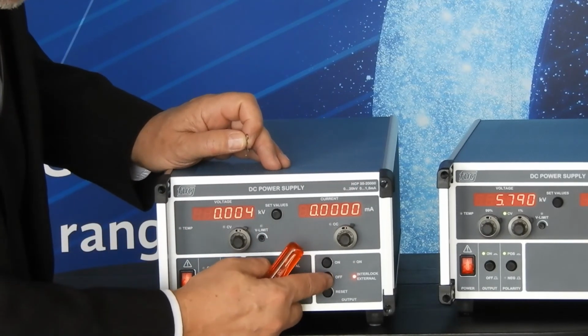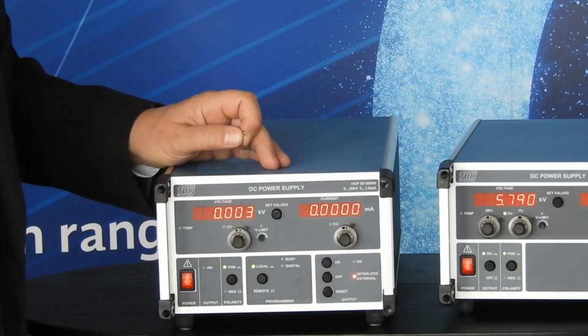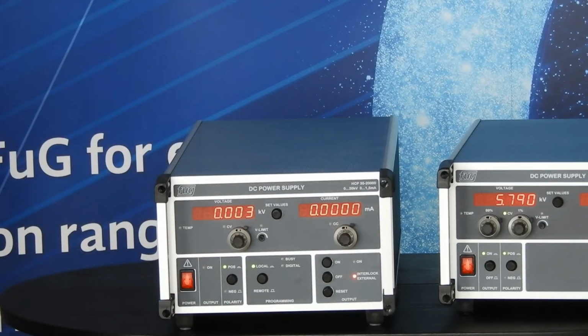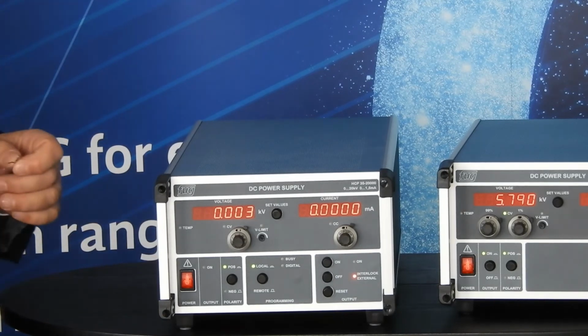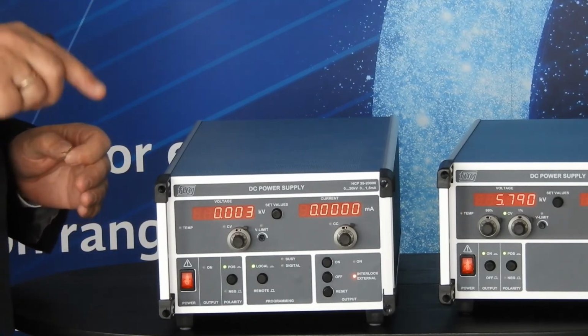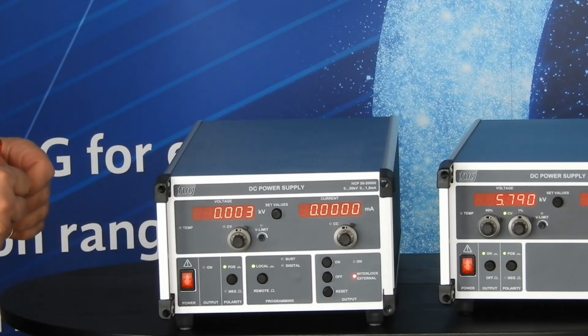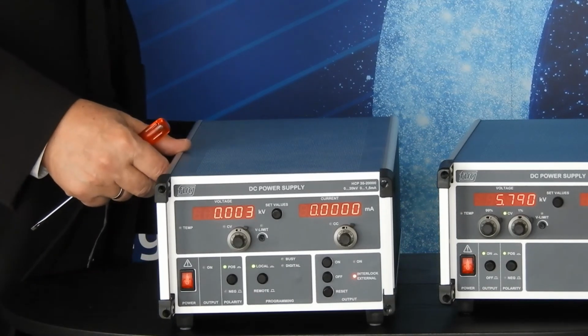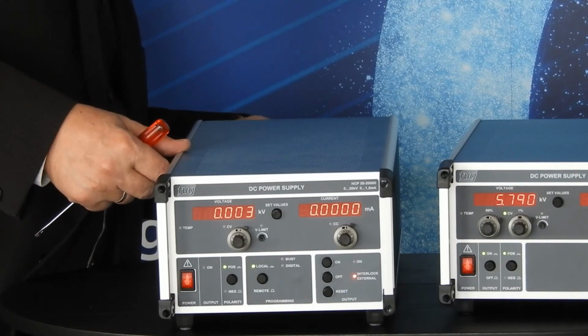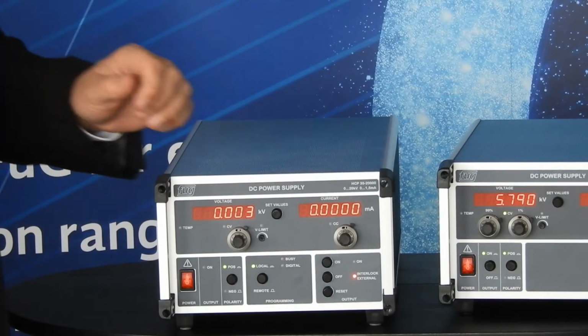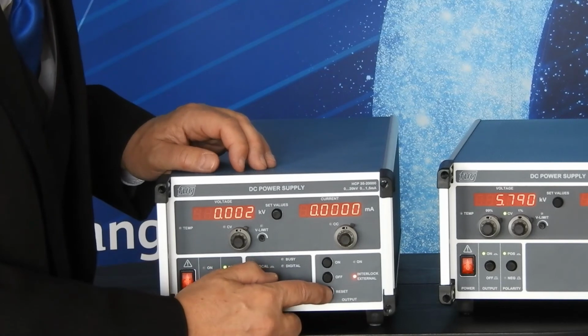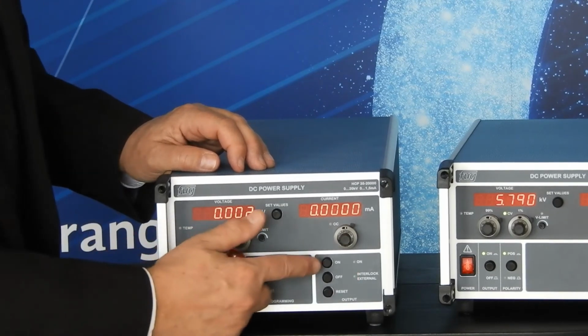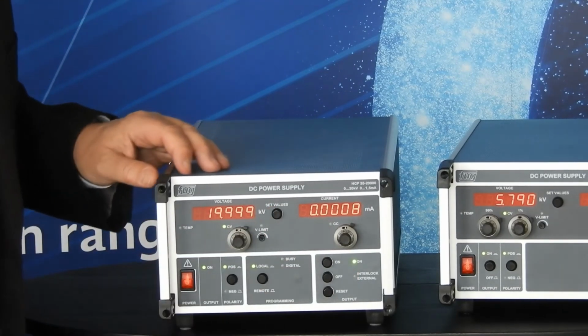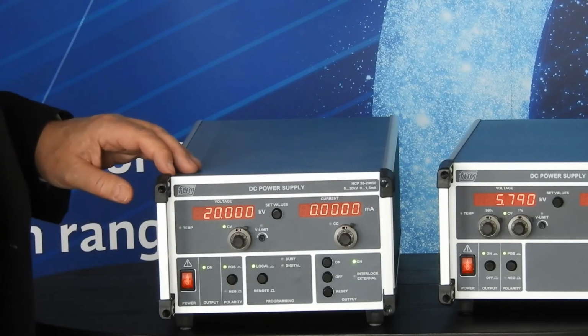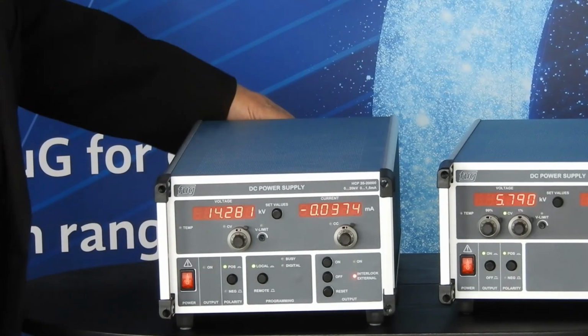But it has switched off now, and it's not possible to switch it on again. If you push the on/off button, it doesn't go on, and it's also not possible to switch it on via interface or otherwise. Only after the interlock loop, the connection between these two pins of this socket, has been restored. I push the bridge now. Then you can push the reset button, and then you can push the on button, and the power supply will go on again.